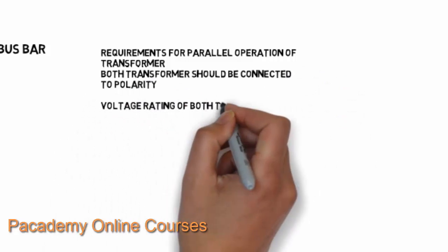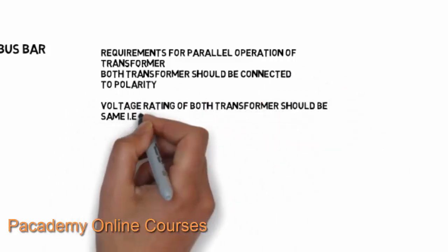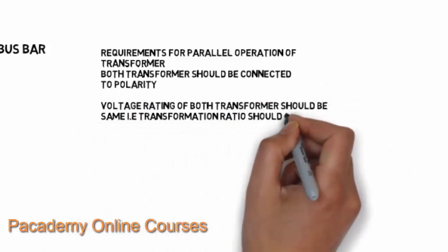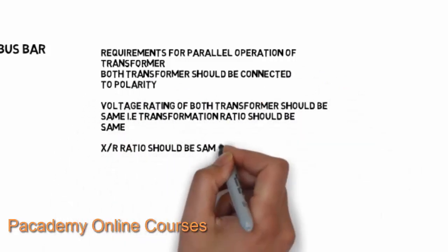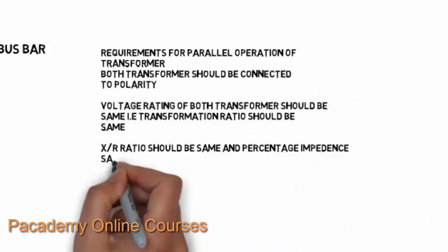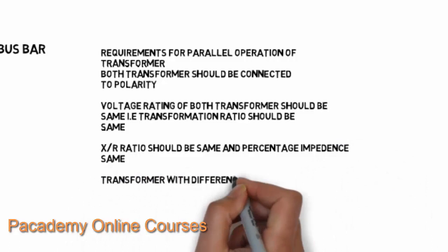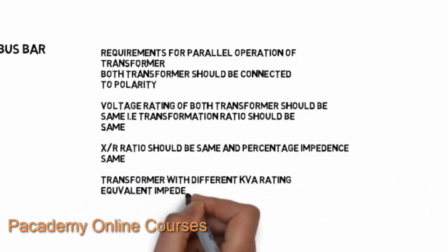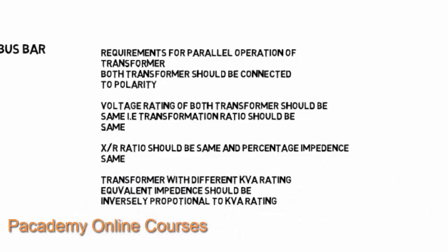The requirements for parallel operation of transformers include that both transformers should be connected with correct polarity — the primary and secondary windings should have the same polarity. Also, the voltage rating of both transformers should be the same, meaning the transformation ratio should also be the same.